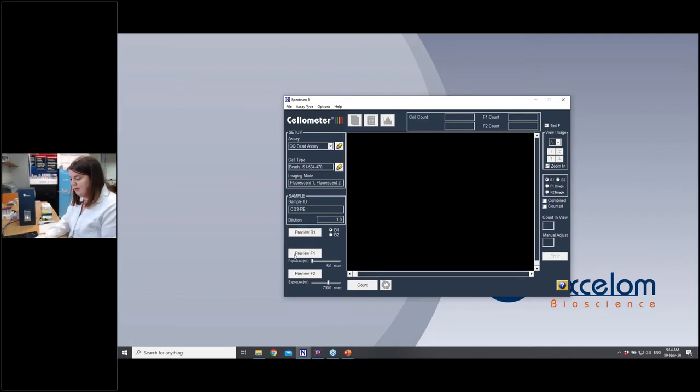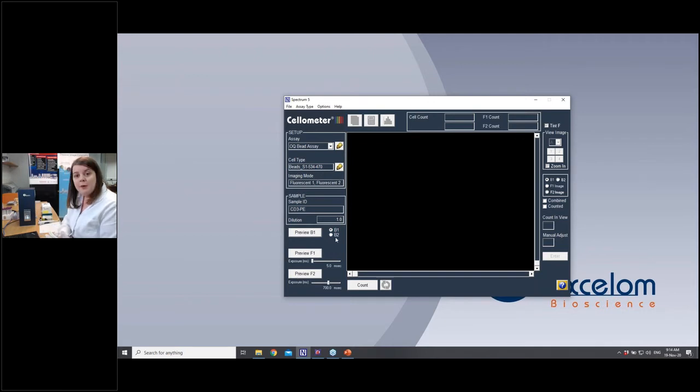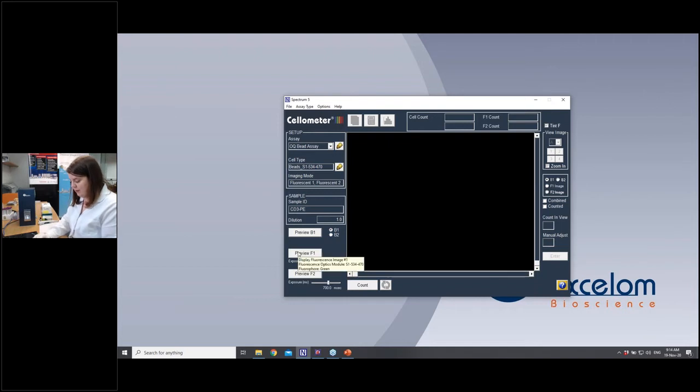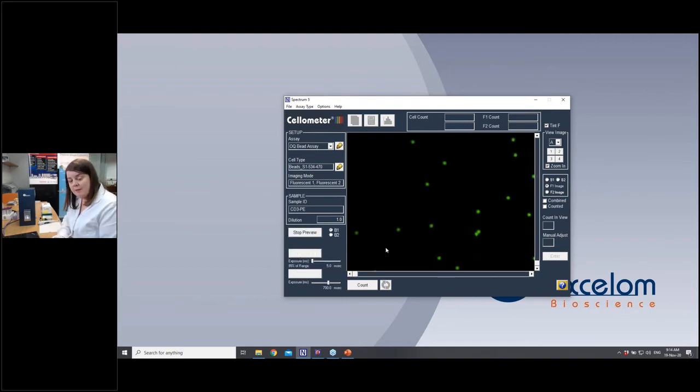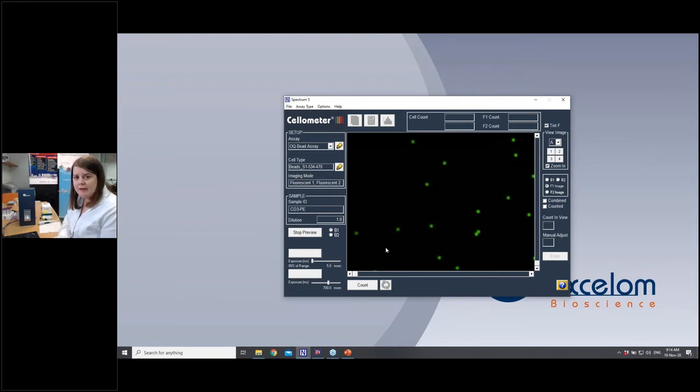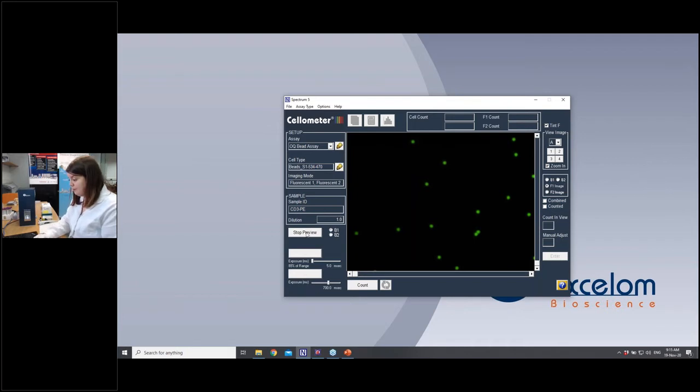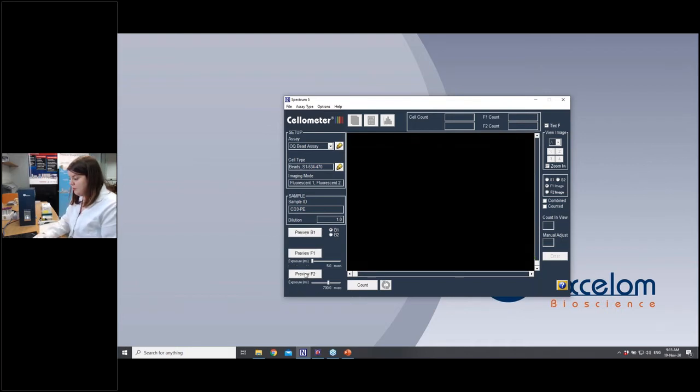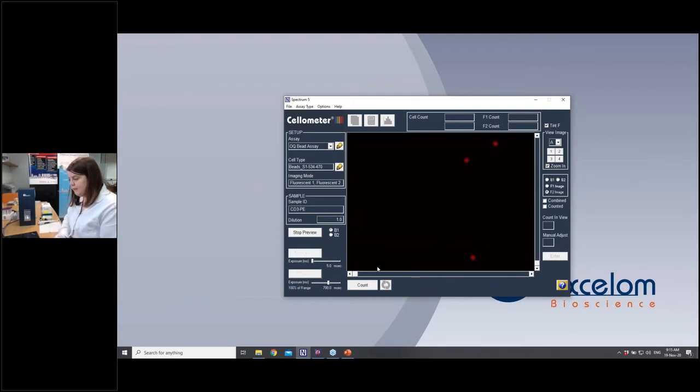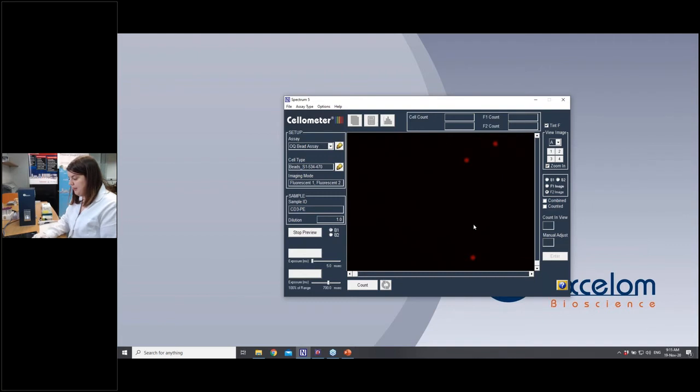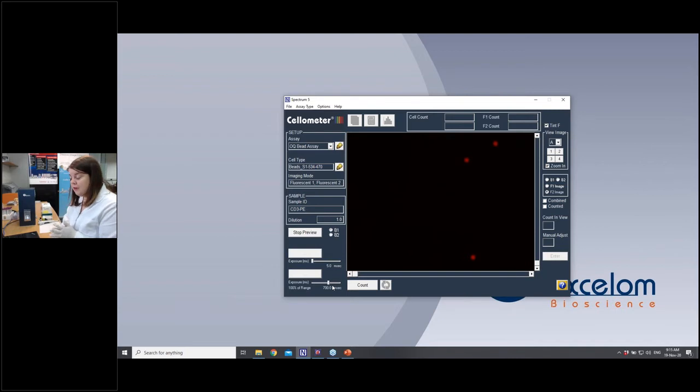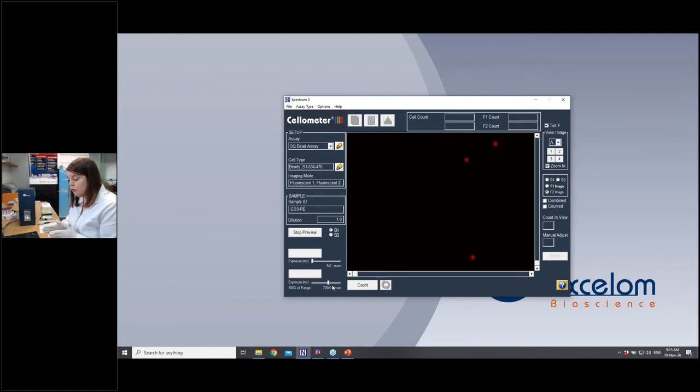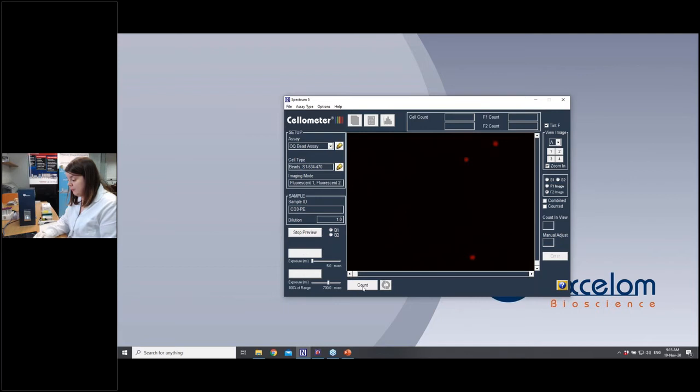I can then stop that preview and I can also preview in either of the fluorescent channels. The two I've got installed at the moment are a green filter and a red filter. So if I preview in F1, I should see the green image of those beads. This would mimic looking at the live portion of your cells if you were doing viability. And you could also look at the red image as well. So you might hear the noise. It's just the changing of the filters and then you can see your red image there. The exposures can be changed. You can make things brighter. You can make things dimmer depending on how strong your staining is. It's particularly important when you're doing antibody staining to have that control. But once you're happy with the focus and the exposure, you can press count.